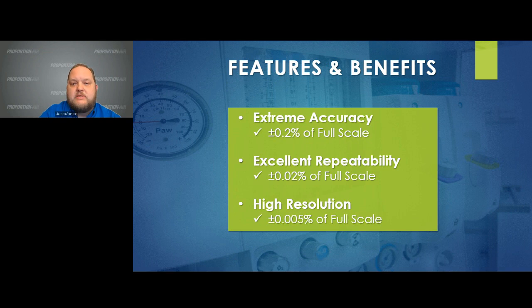For applications with extremely tight tolerances, our high resolution proportional regulators, which we will get to later, are a great choice. Pressure is held at the necessary level, and the leakage at that pressure is then actively measured by a flow transducer. The smooth, steady control of the proportional solenoid results in an error-free flow transducer output.